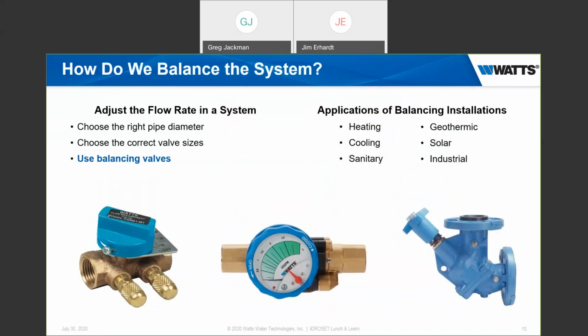So you may notice on this screen, if you're familiar with Watts products, all the way on the left, you'll see our CSM 61 circuit setter. That is a static balancing valve as well. And as you know, for those of you who have done balancing before, that requires the use of an external instrument known as a digital manometer, where you measure the pressure differential across that valve. And by knowing the CV value of the valve, CV basically meaning the flow rate that's required to create 1 psi of pressure drop, by measuring the pressure differential, the instrument can then calculate what the flow is through that circuit.